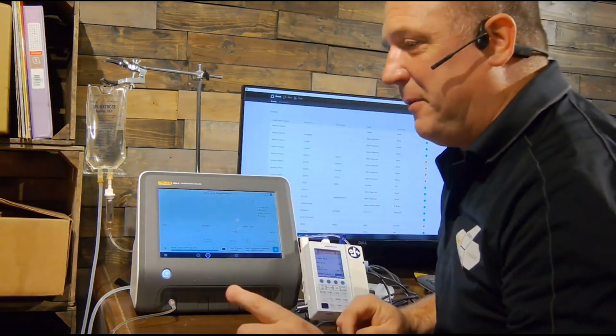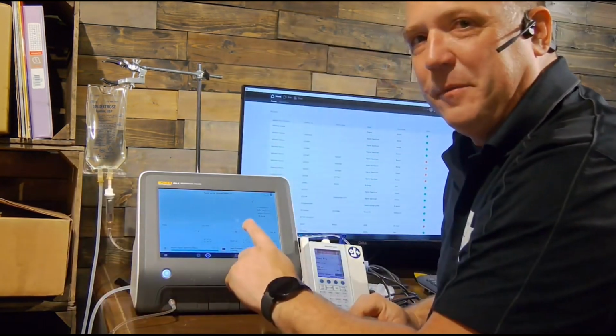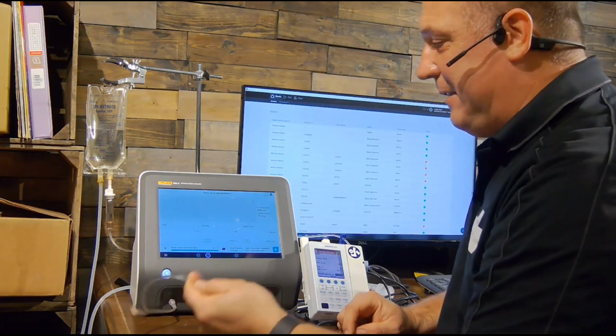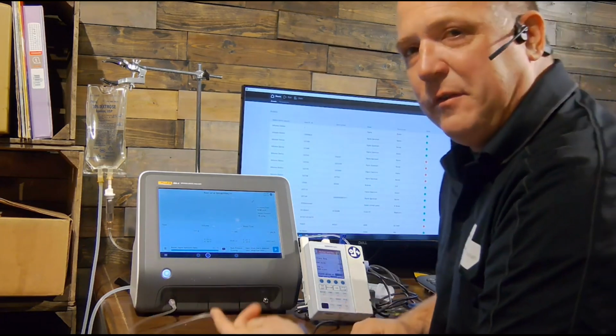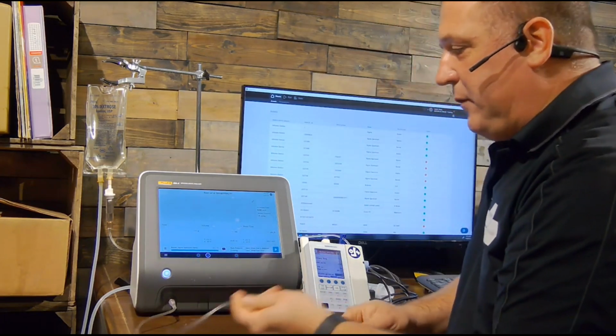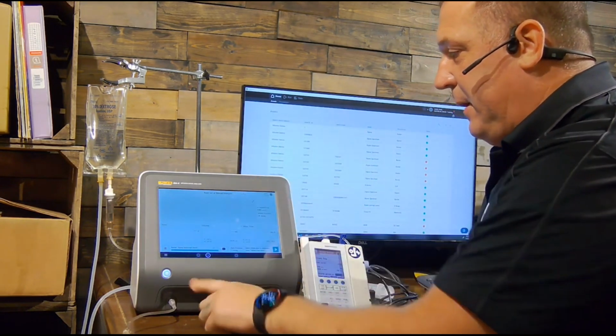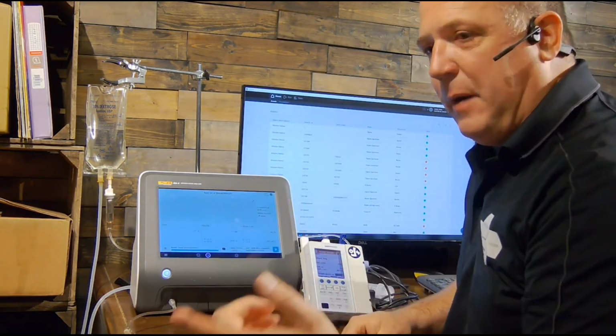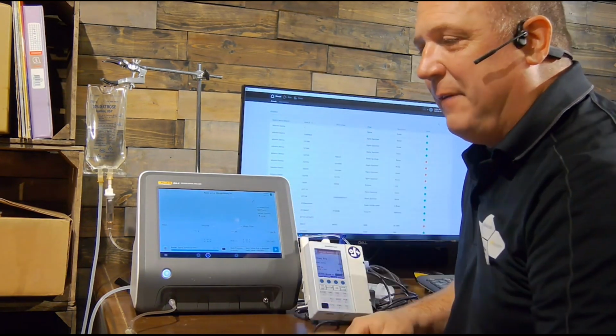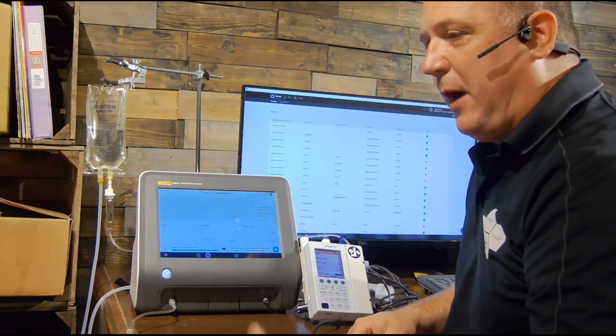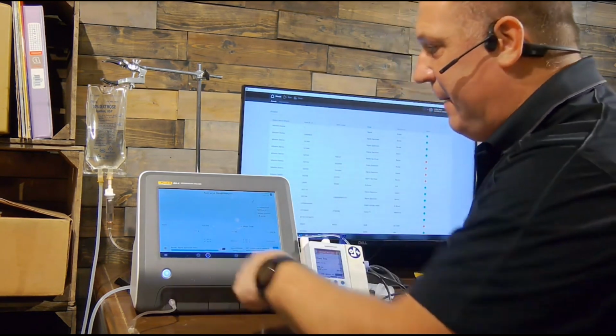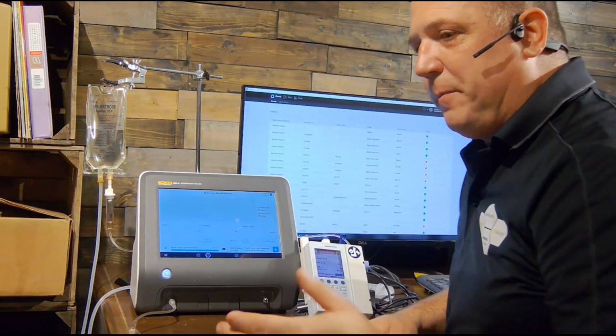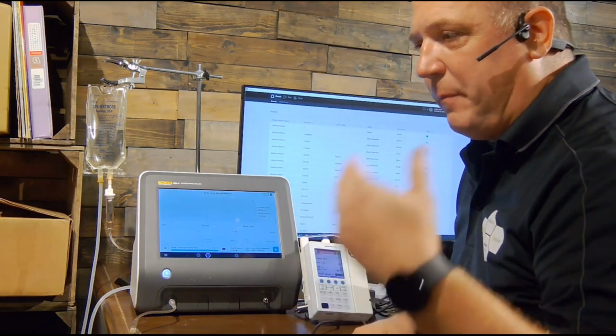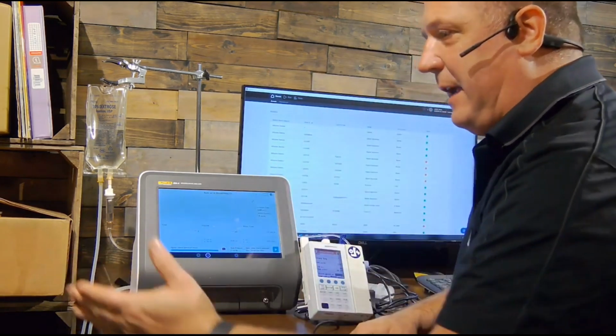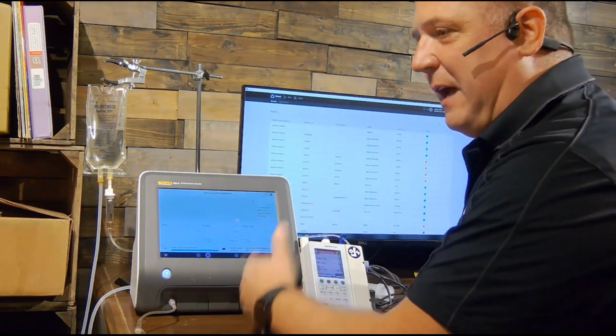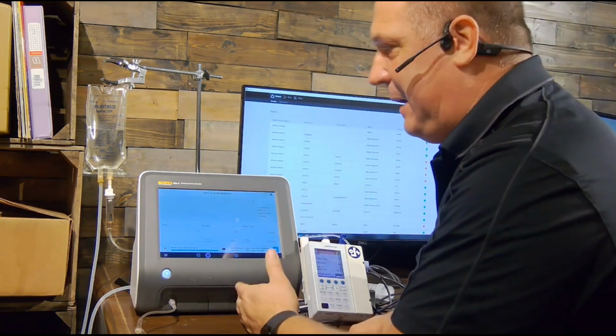All right, so my infusion pump is set up. Now you notice something here. I didn't have to prime the system. The reason I didn't have to prime it is since this uses a piston-driven stepper motor, once I pushed all the fluid through here, there's no more air bubbles. So I only had to prime one time. It's not like the IDA-5 or the 4 where I used to lose my prime in between each of the tests. I already did it. So some of those PMs like the Alaris, where that's built into it, go ahead and just let it do its thing, but you don't have to do it to satisfy the IDA-6's needs anymore.